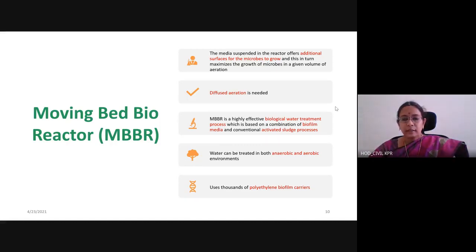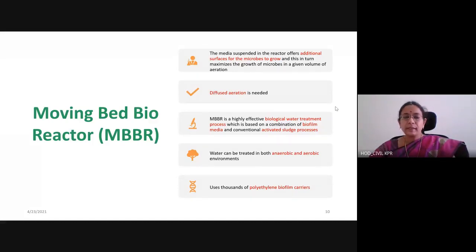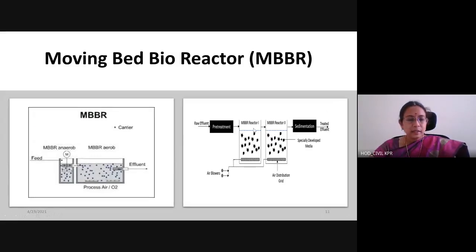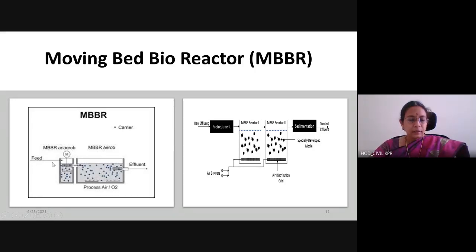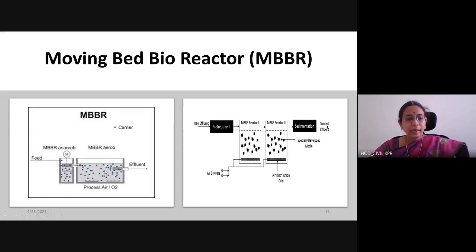A special feature of MBBR is that water can be treated in both anaerobic and aerobic environments — whereas in SBR, only aerobic process is used. In MBBR, both anaerobic and aerobic treatments can be done. Thousands of biofilm carriers are used. You can see the small dot-like things in the picture — those are the biofilm balls. This MBBR combination type: the inlet is fed in, there is no aeration provision in the anaerobic zone, and then it can be sent to the aerobic process where diffused aeration is provided at the bottom along with biofilm. This comprises both anaerobic and aerobic treatment.